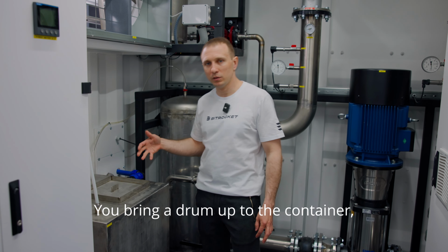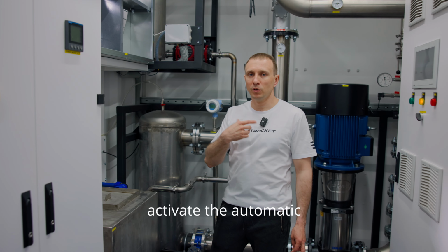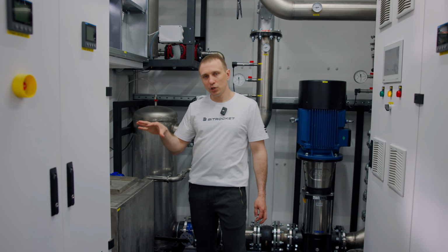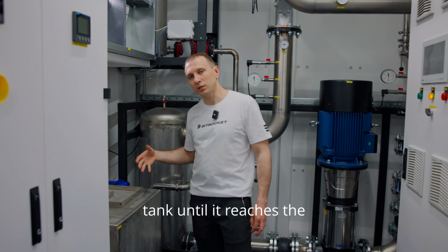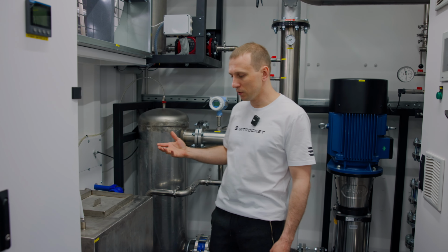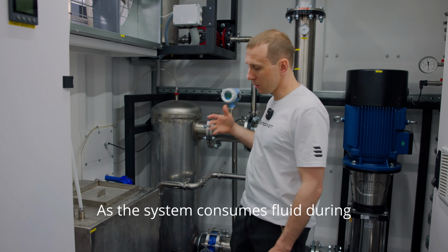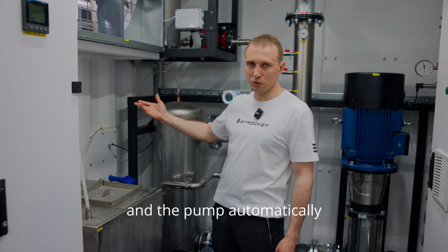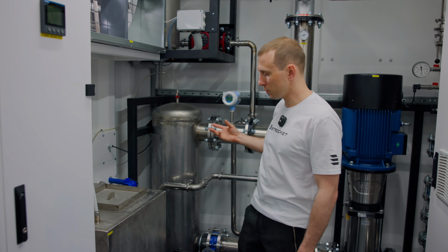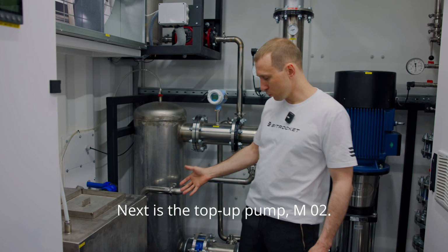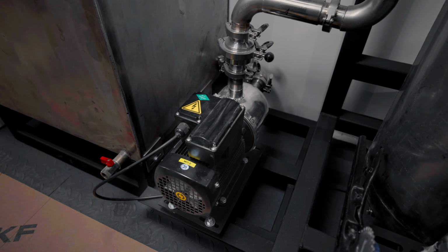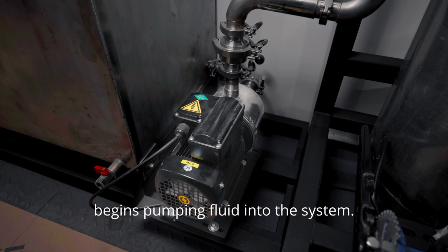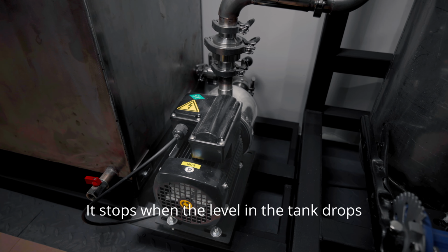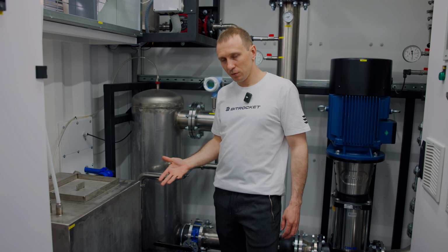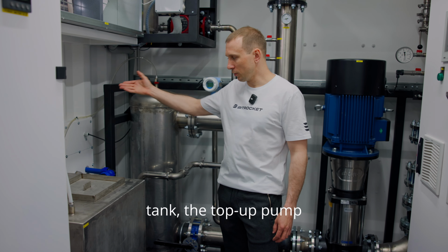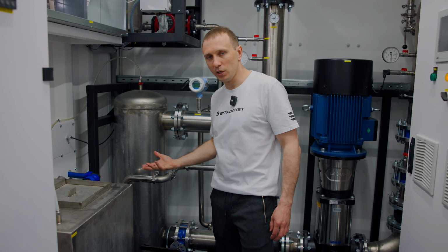You bring a drum up to the container, connect it, turn on the pump, and activate the automatic filling mode. Using level sensors, the pump fills the tank until it reaches the upper level, then stops. As the system consumes fluid during operation, the level drops and the pump automatically refills the tank. Next is the top-up pump, MO2. When switched to automatic mode, it begins pumping fluid into the system. It stops when the level in the tank drops to the minimum threshold. As soon as the external pump refills the tank, the top-up pump restarts automatically.